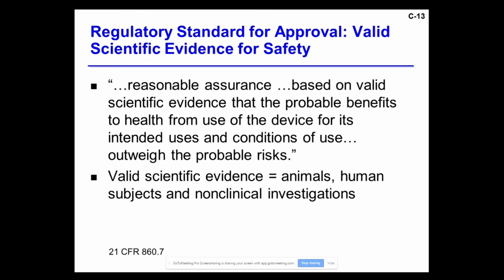The regulatory standard for approval for safety is that you have to show that there's reasonable assurance that the benefits with the intended use outweigh the risks. And you need to show valid scientific evidence, and that has to include animal studies, human subjects, and also non-clinical investigations, which are known as bench testing. So you have to show that the device will consistently perform as expected under extreme conditions like high temperature, like 50-foot drops, like having somebody stamp on it and such.